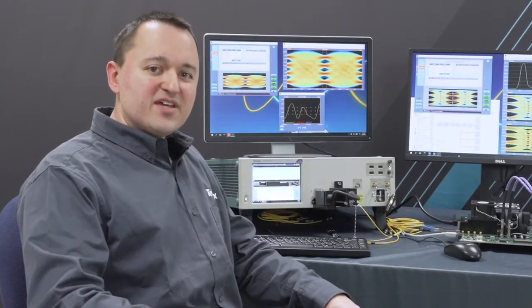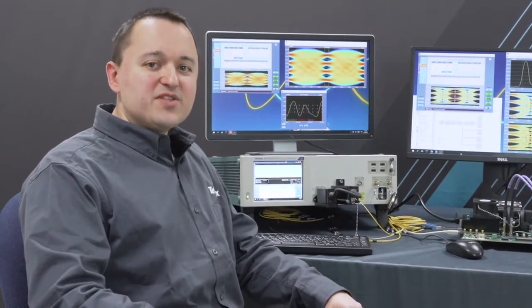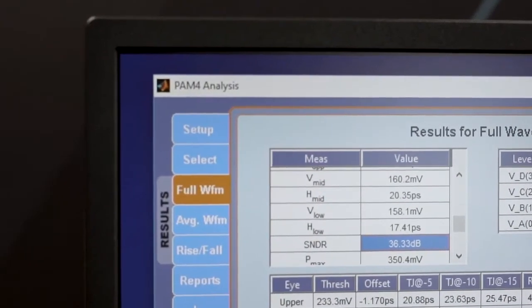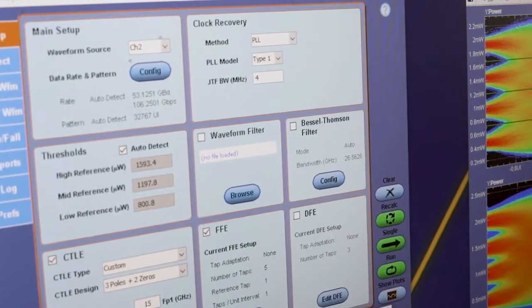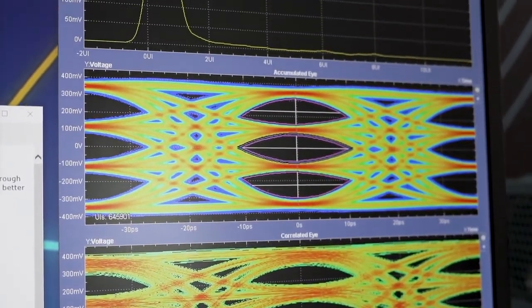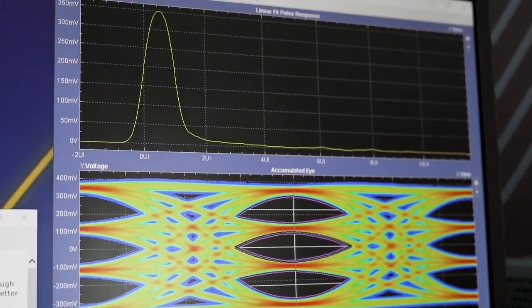Once you have the signal going into the oscilloscope, you can then use the PAM4 analysis software to analyze it. The PAM4 analysis software features powerful software clock recovery specifically designed for PAM4 and recovers the clock directly from the signal itself without the need for an additional clock recovery unit.